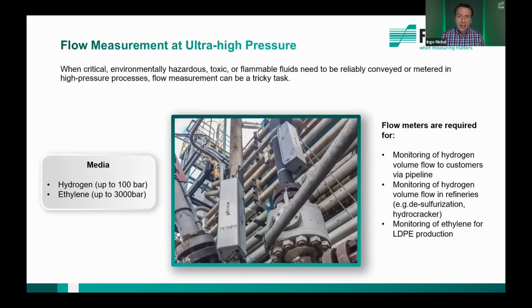A lot of hydroprocessing processes in petrochemical plants run at elevated pressure conditions. Hydrogen is used in several applications for cracking or desulfurization tasks. But a very impressive example, which we have in our application database, are the extreme conditions which can be found in LDPE plants, where we have hypercompressed ethylene at above 1,500 to 3,000 bar to produce low density polyethylene. And particularly this example shows the extraordinary measuring capabilities of a non-intrusive flow measurement equipment.